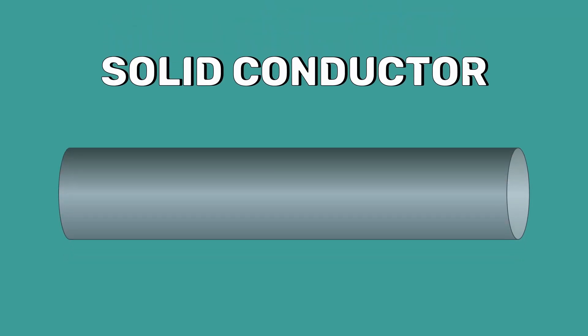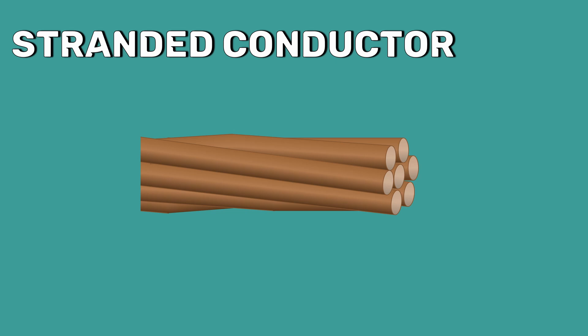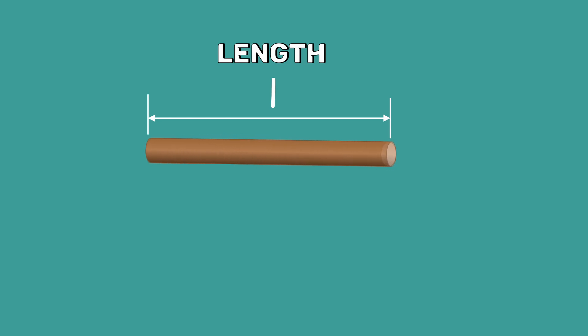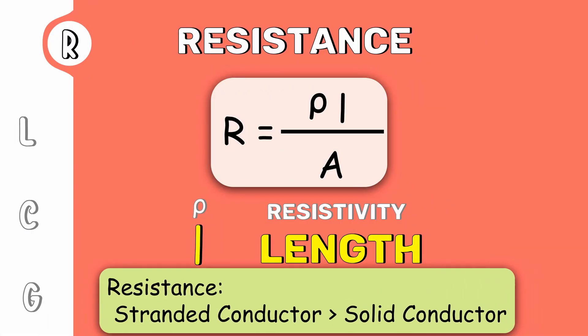Instead of a single solid conductor, we use a stranded conductor in transmission lines. For stranded conductors, alternate layers of strands spiral in opposite directions. Spiraling makes the strands one or two percent longer than the actual conductor length. Therefore, the resistance of the stranded conductor is slightly more than the solid conductor of an equivalent cross-sectional area.